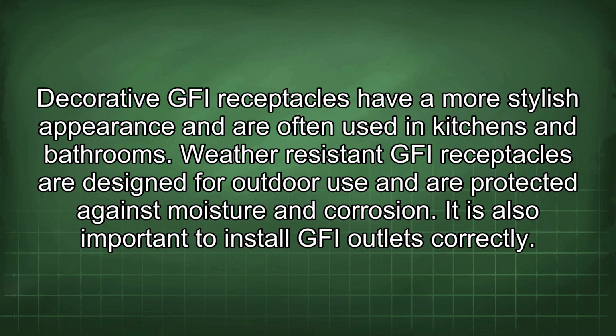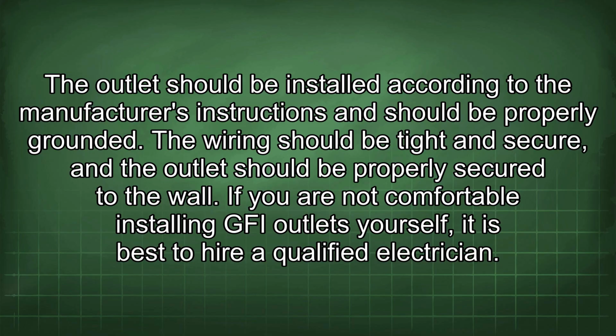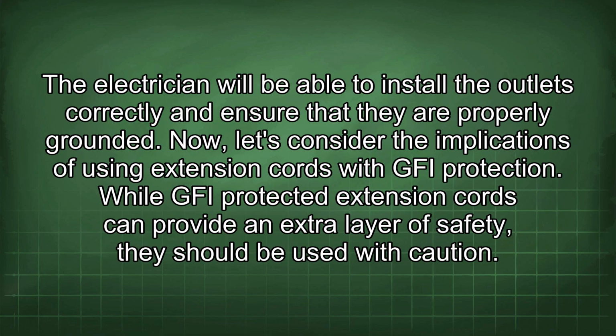It is also important to install GFI outlets correctly. The outlet should be installed according to the manufacturer's instructions and should be properly grounded. The wiring should be tight and secure, and the outlet should be properly secured to the wall. If you are not comfortable installing GFI outlets yourself, it is best to hire a qualified electrician. The electrician will be able to install the outlets correctly and ensure that they are properly grounded.